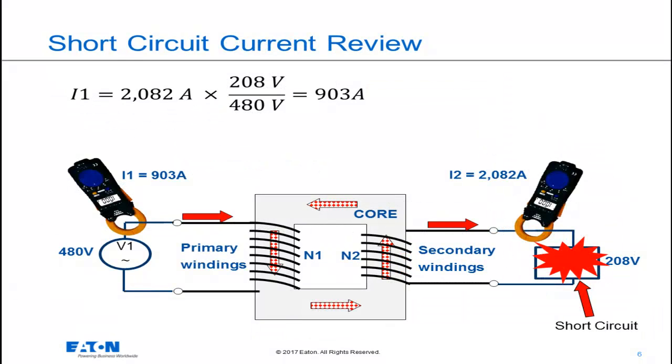This is just a different way of looking at that exact same calculation that we just made. During this faulted condition, if I place a current meter in the secondary and primary conductors of this transformer, the ammeter on the secondary would read 2082 amps, the current being delivered to the short circuit. The ammeter on the primary would read 903 amps, which is calculated in the equation at the top side of this slide.